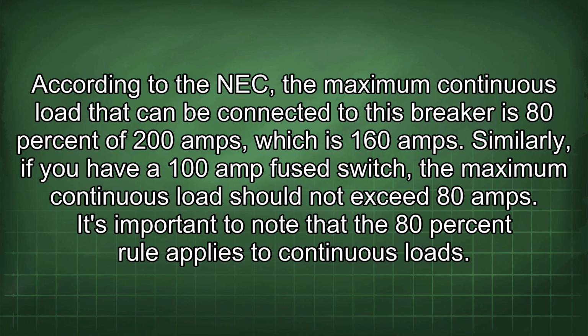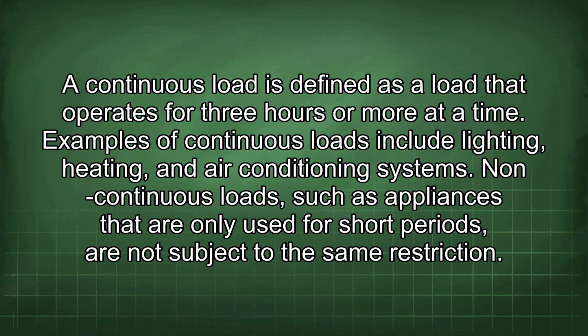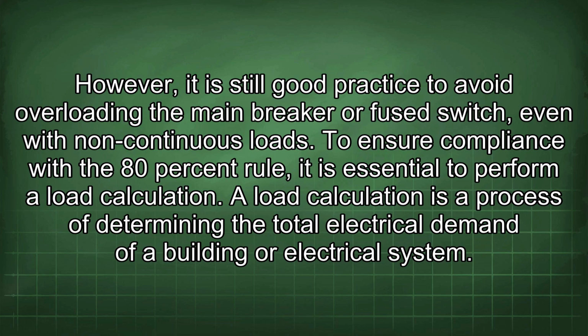80 amps. It's important to note that the 80% rule applies to continuous loads. A continuous load is defined as a load that operates for 3 hours or more at a time. Examples of continuous loads include lighting, heating, and air conditioning systems. Non-continuous loads, such as appliances that are only used for short periods, are not subject to the same restriction. However, it is still good practice to avoid overloading the main breaker or fuse switch, even with non-continuous loads.